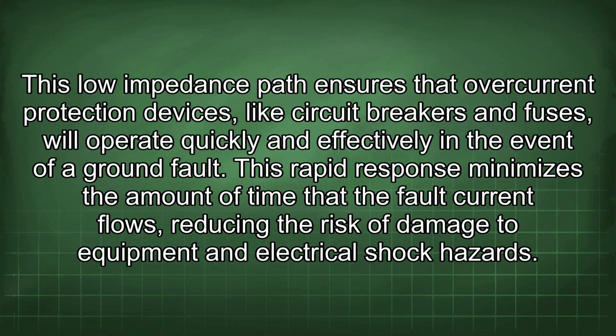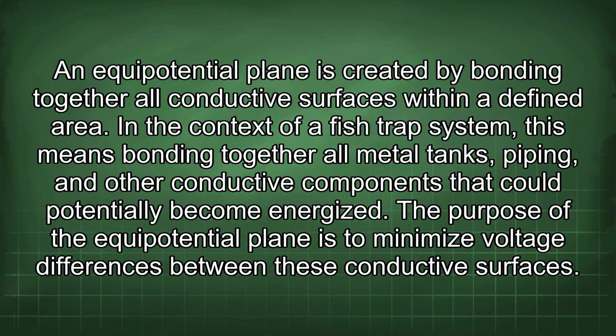This low impedance path ensures that overcurrent protection devices, like circuit breakers and fuses, will operate quickly and effectively in the event of a ground fault. This rapid response minimizes the amount of time that the fault current flows, reducing the risk of damage to equipment and electrical shock hazards. An equipotential plane is created by bonding together all conductive surfaces within a defined area.